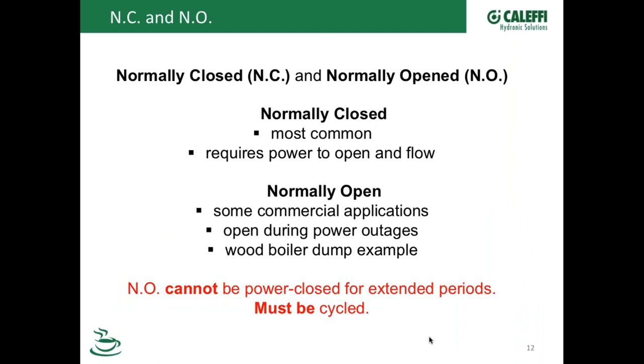Also on the Z1 zone valve, the center valve that I just showed you, our spring return valve, it's available with a normally open and a normally closed function to it. So basically what a normally closed valve is when there's no power being applied to that valve. Let's say you've got a 24 volt valve. There's a call for heat from the thermostat, goes through the relay board, opens that valve, flow goes through it, it makes the end switch, starts up the pump if you require an end switch on it. A normally open valve is open all the time, and when you apply power, it closes that valve.